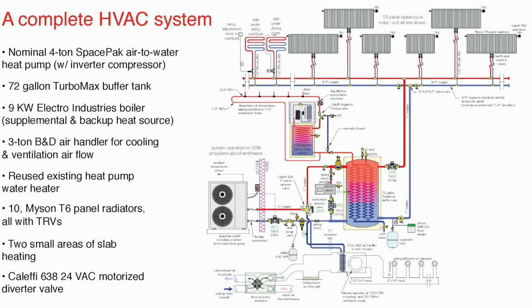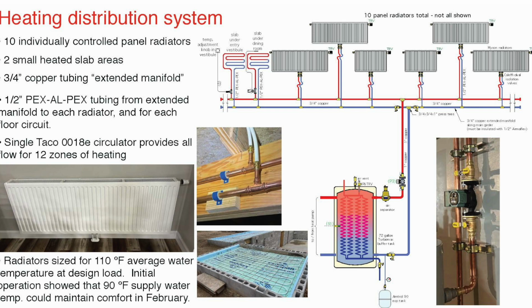This just shows you, so I'm going to talk about this more this afternoon. I won't spend a lot of time on it here, but this integrates space heating, cooling, domestic hot water heating, and heat recovery ventilation. I'm a big proponent of hydronic professionals adding heat recovery ventilation to their offerings. Now you've got a complete system. You're dealing with the heating, the cooling, domestic water, and you're dealing with a very important thing, indoor air quality. Okay? So that's a complete system offering. Again, I will talk about this more this afternoon, how we put it together, but this is a system where the panel rads are running on 90-degree water in February in upstate New York.